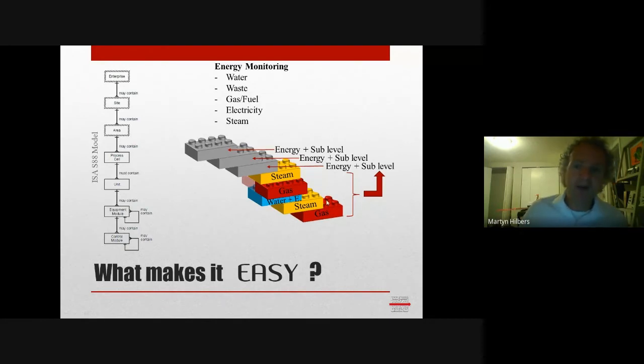Now, going further on the simplified architecture and the ability to pull information through that architecture, one of the other pieces of information that is pushed through is operator information. By linking these software modules together, the operator is told, okay, you're in step 5 of your sequence, and in this step, your pump is starting, or you've got a problem at step 10. All that information is automatically pushed through by just linking these software modules together. In a conventional system, you would have to program that up. In a PLC-Easy solution, that's automatically done because you link them together through those 8 parameters.